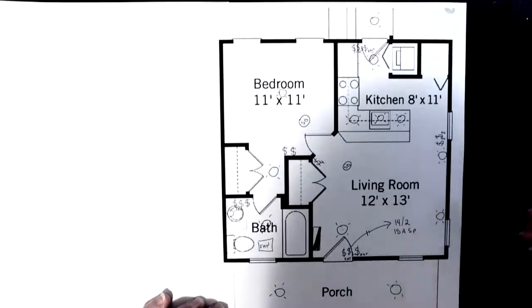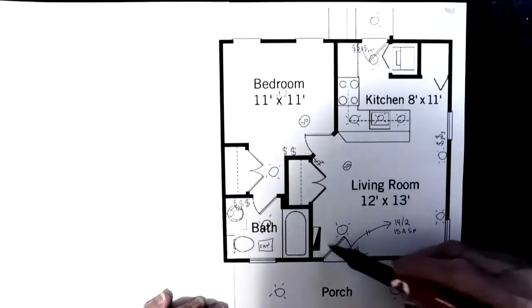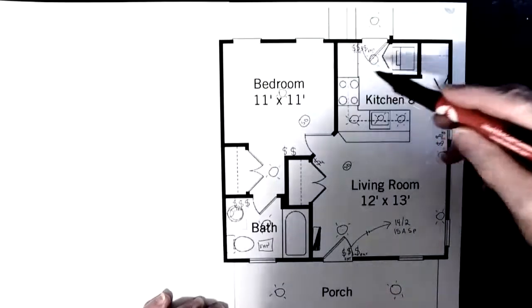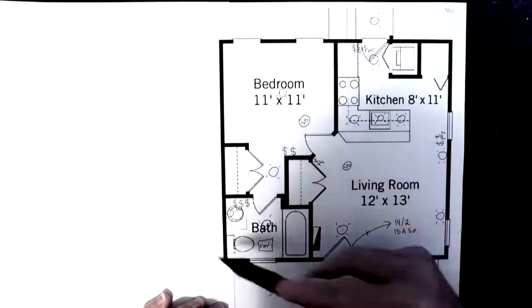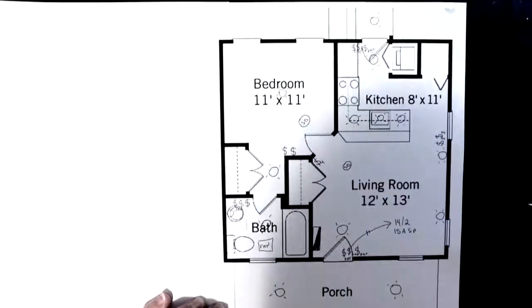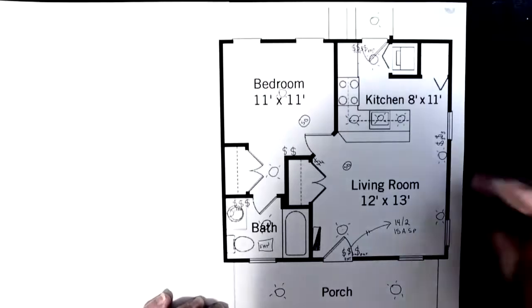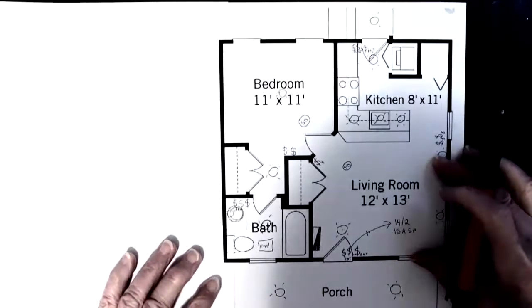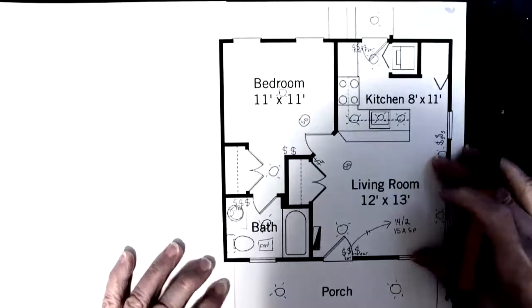Now I counted, and I have more than 12 in total. So I'm going to end up with two home runs. I'm going to split those home runs. I'm going to go from the panel this direction around the house, and then from the panel this direction around the house. And I'm not going to try to load up these circuits to their max. I'm just going to try to make the wire work, the length of wire work, to minimize my wire.